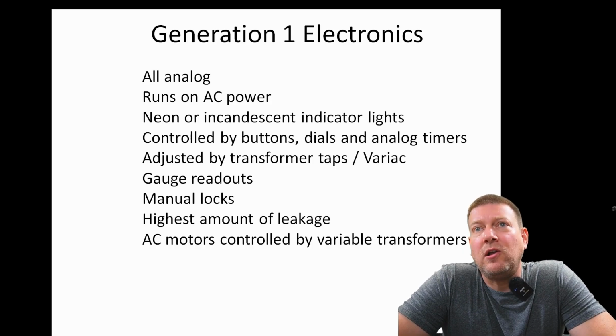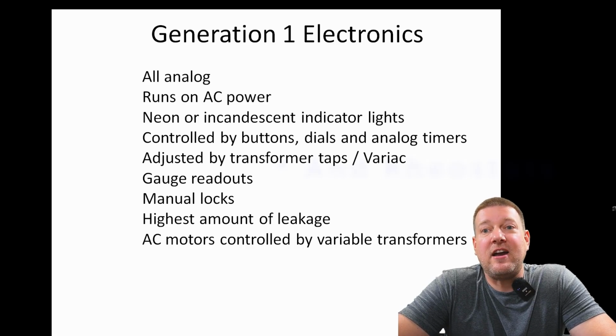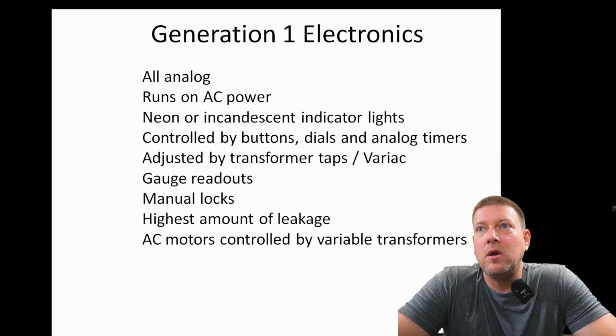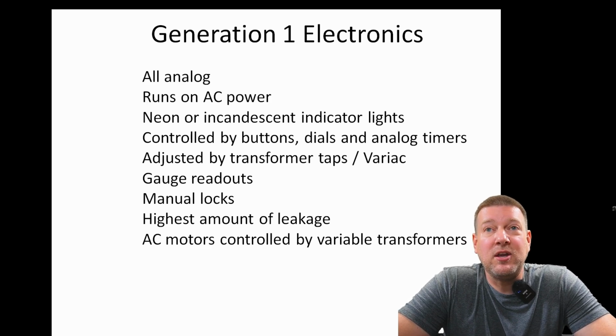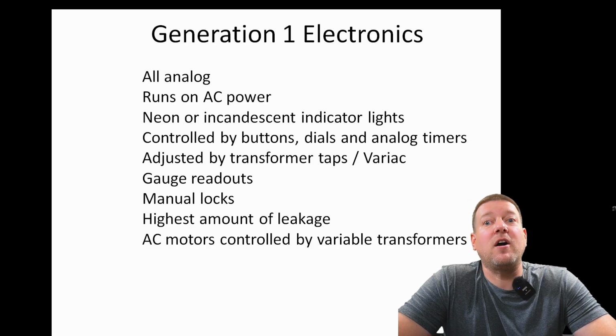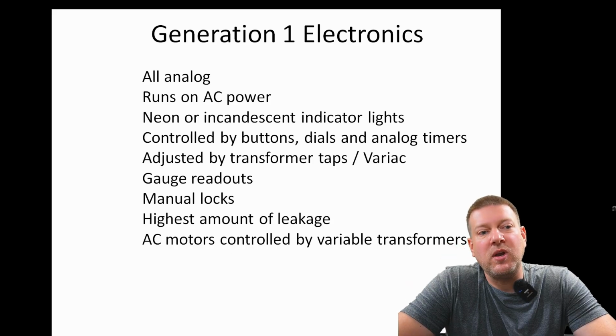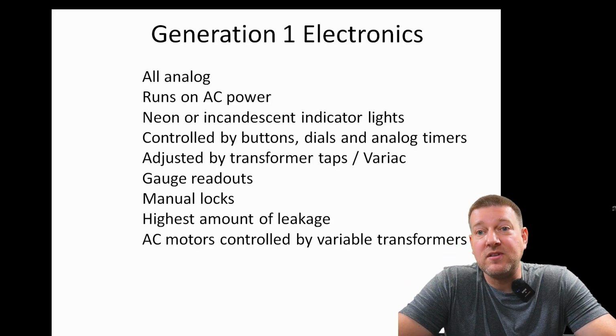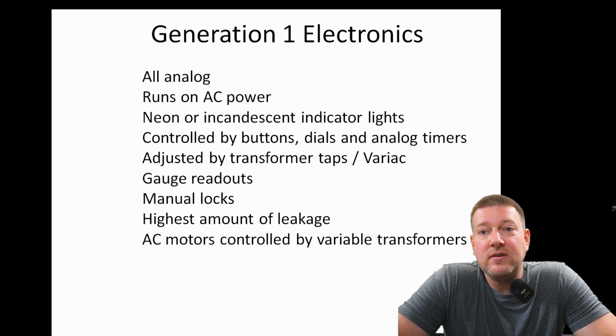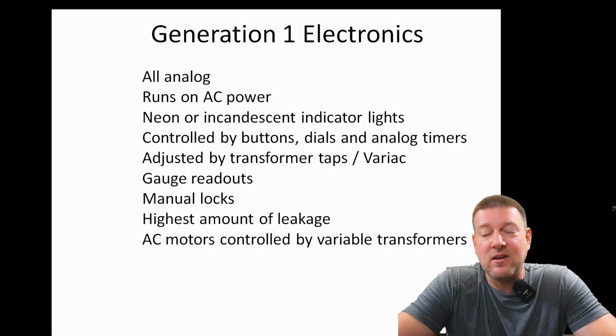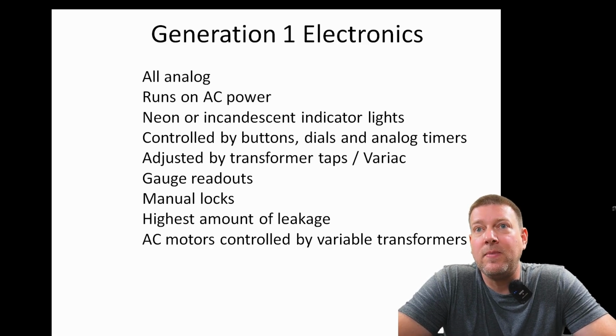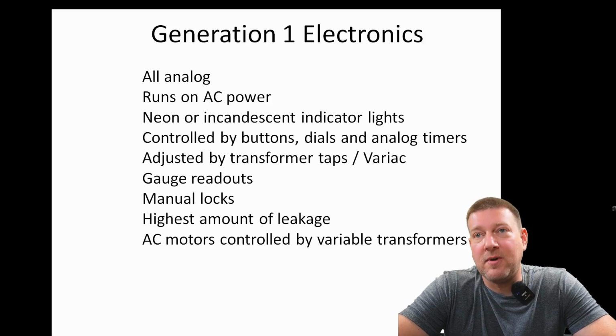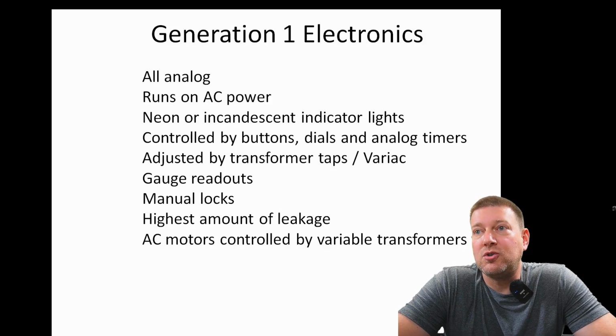They're controlled by buttons, dials, and analog timers. They're adjusted by transformer taps and variacs. A variac, I might have one around here, is basically an adjustable AC power source, so you can tune it down or tune it up. You can also change the transformer taps, which control the voltages. They usually have gauge readouts. We have manual locks, interlocks. An interlock is normally like a button or a switch that detects if a panel is there, usually a micro switch. When it is disengaged, it opens the mains and the rest of the circuit is not energized. You see this in some of the old light sources, okay? So it will have an interlock on the cabinet which disconnects the mains. And like I said earlier, they have the highest amount of leakage, right? So they have AC motors, which are controlled by variable transformers.